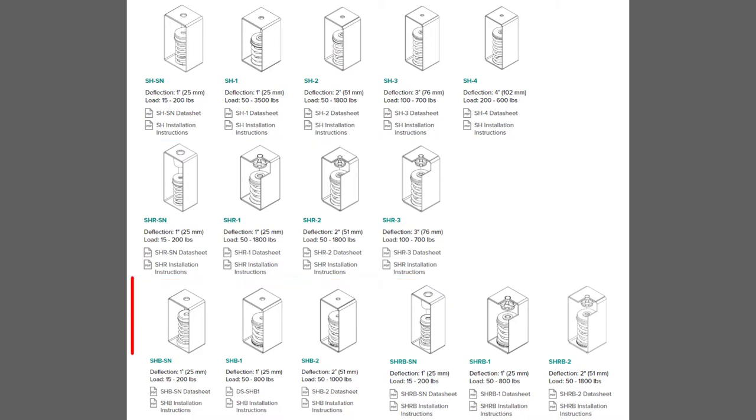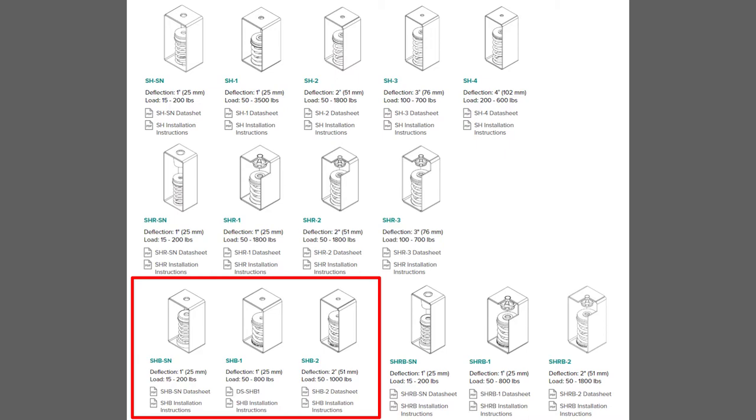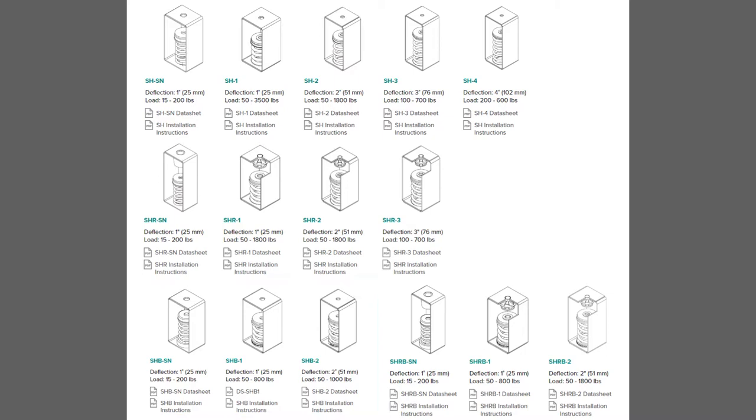The next group of isolators is like the SH isolators but with the addition of a rubber cup under the spring that provides some isolation for higher frequencies as well as better protection against misaligned hanger rods touching the hanger box.